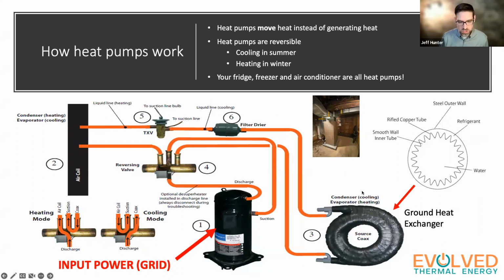The second component, different from an air conditioner or refrigerator, is our source coil, or coax. If I were to cut that coil, I'd see a cross section like this. On the inside is where my loop fluid runs — that mixture of water and antifreeze — and on the outside is where the refrigerant is. It has a rifled profile on purpose, to encourage heat transfer. If the loop fluid runs through the center and refrigerant is on the outside, we want heat to transfer from the fluid into the refrigerant so it can be carried through the system for heating. In cooling, we reverse this — taking heat from the refrigerant and putting it out to the loop fluid so it can be carried out to the ground loop field.